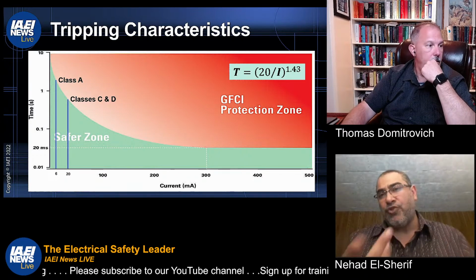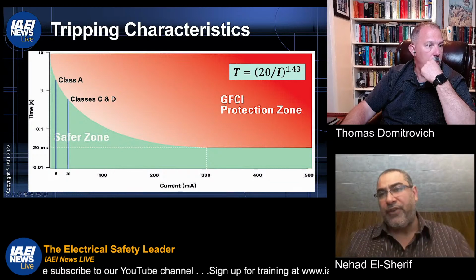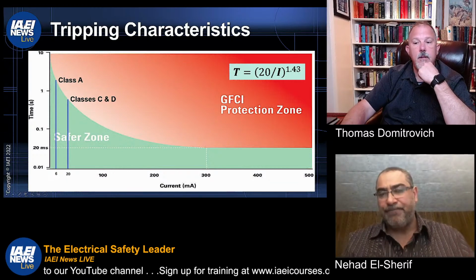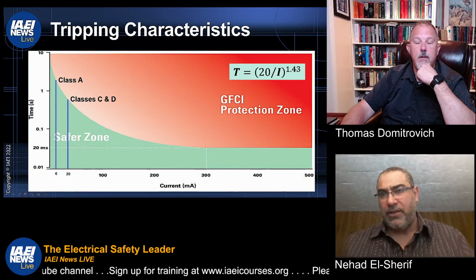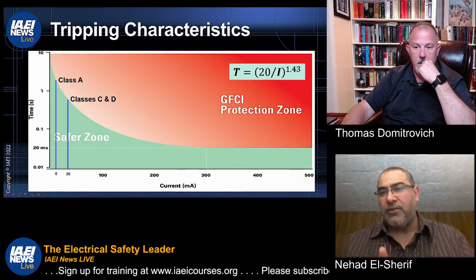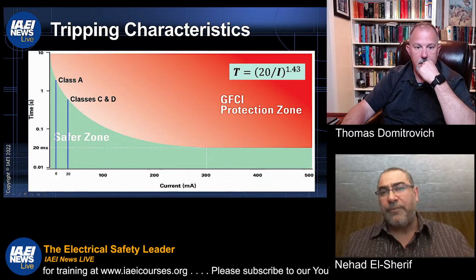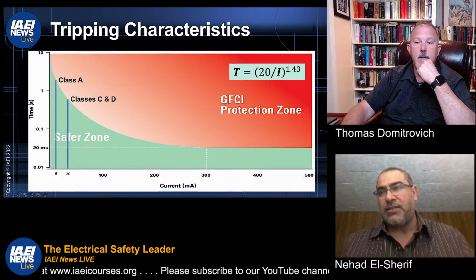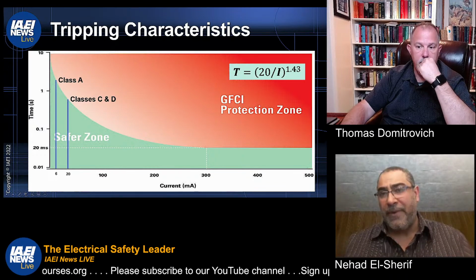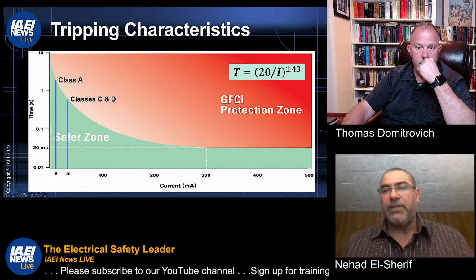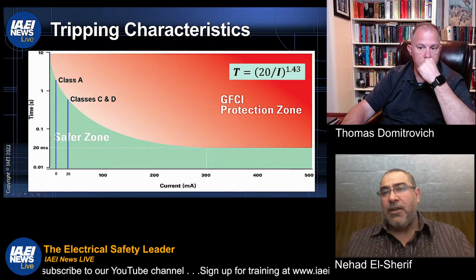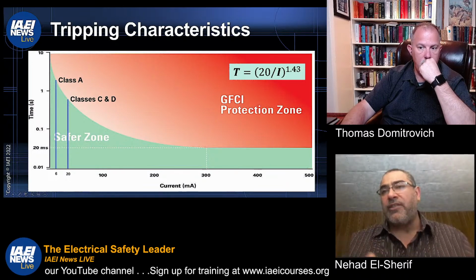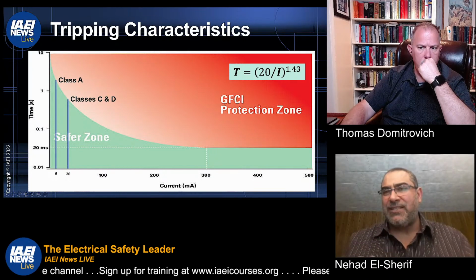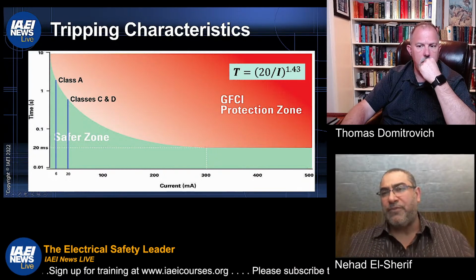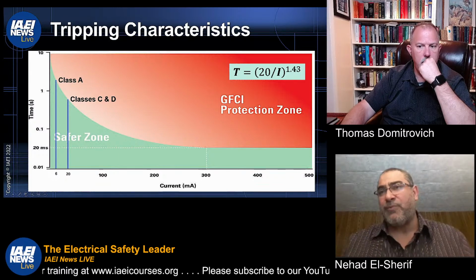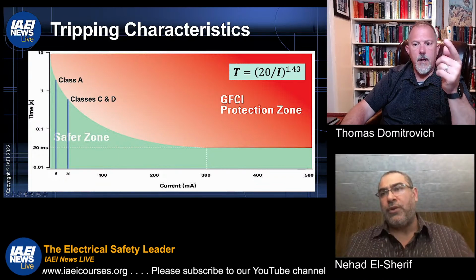The Class E that I mentioned is not shown here. If you notice, the curve gets to a point where it becomes a definite time, so the curve is horizontal, which means that around 300 milliamperes you are not required to trip quicker than 20 milliseconds. This is the quickest time you are required to trip at for Class C, D, and A. The difference with Class E is that when you get to 300 milliamp, you move to another equation. I think, if I remember correctly, it's 6 divided by I to the power 1.43, which makes another inverse time curve, much, much quicker. And this is what I was referring to.